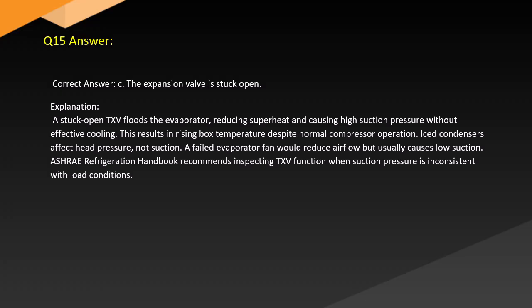Ice condensers affect head pressure, not suction. A failed evaporator fan would reduce airflow but usually causes low suction. ASHRAE Refrigeration Handbook recommends inspecting TXV function when suction pressure is inconsistent with load conditions.